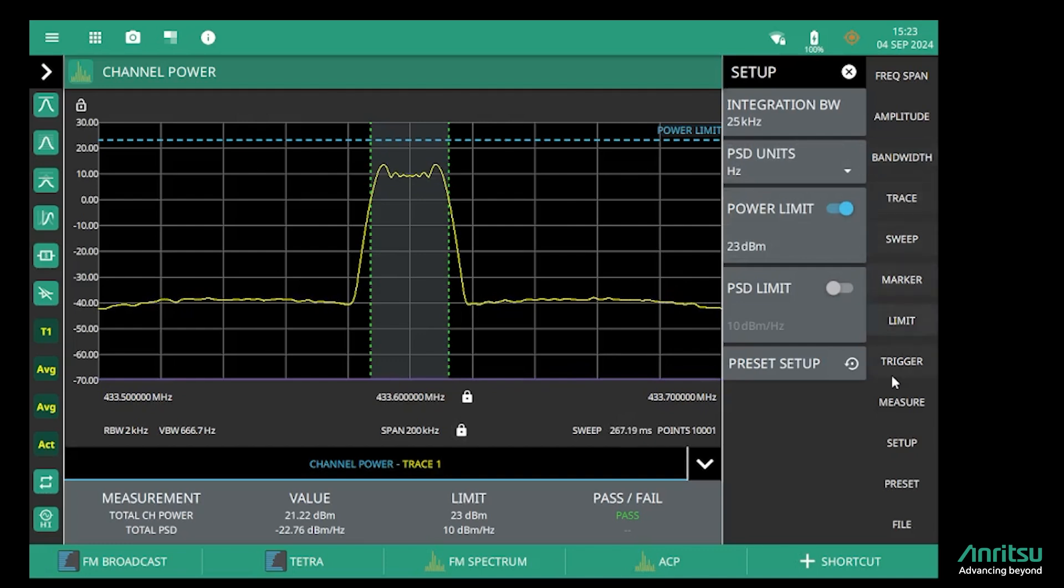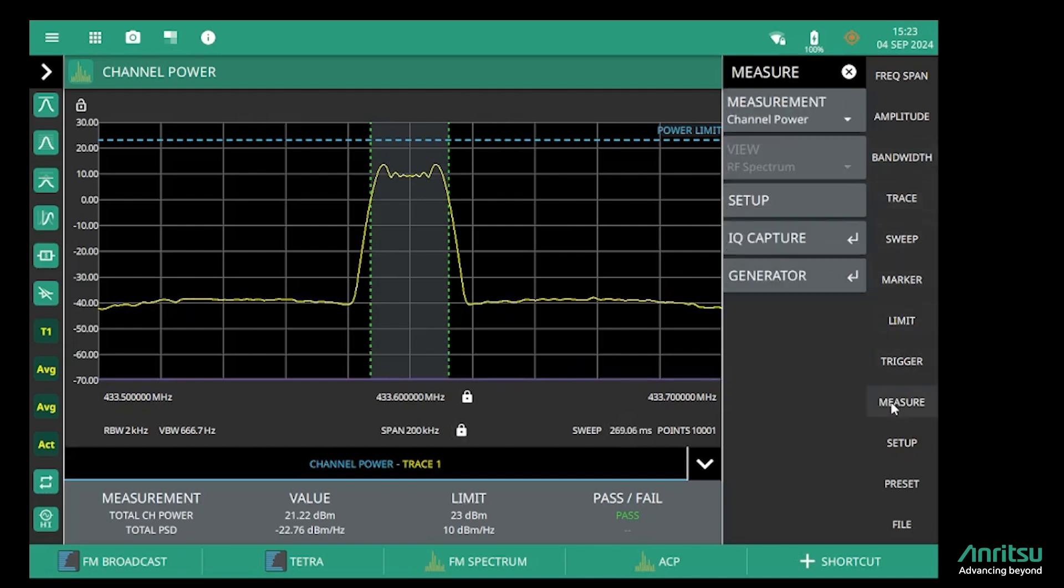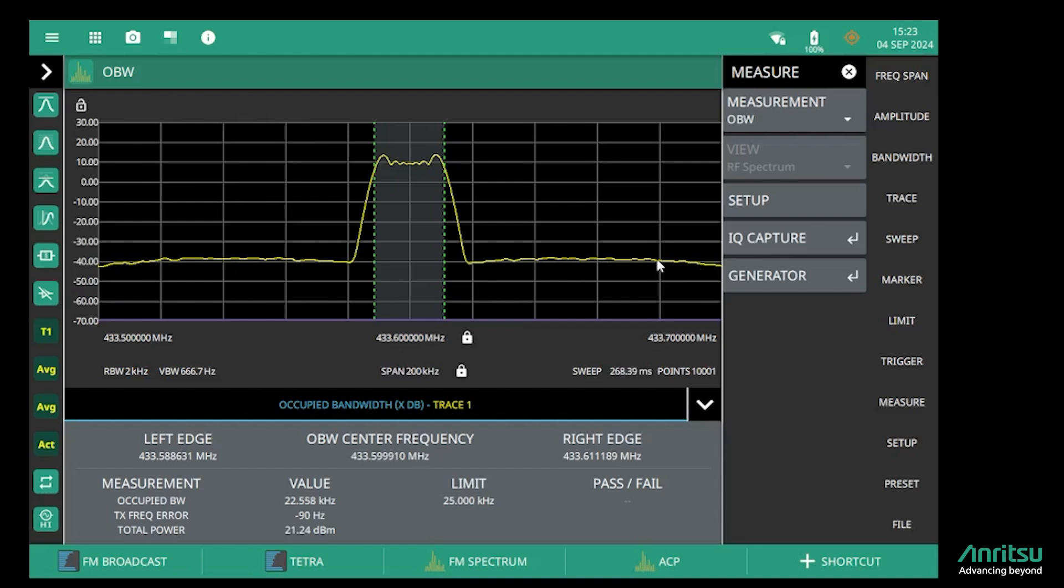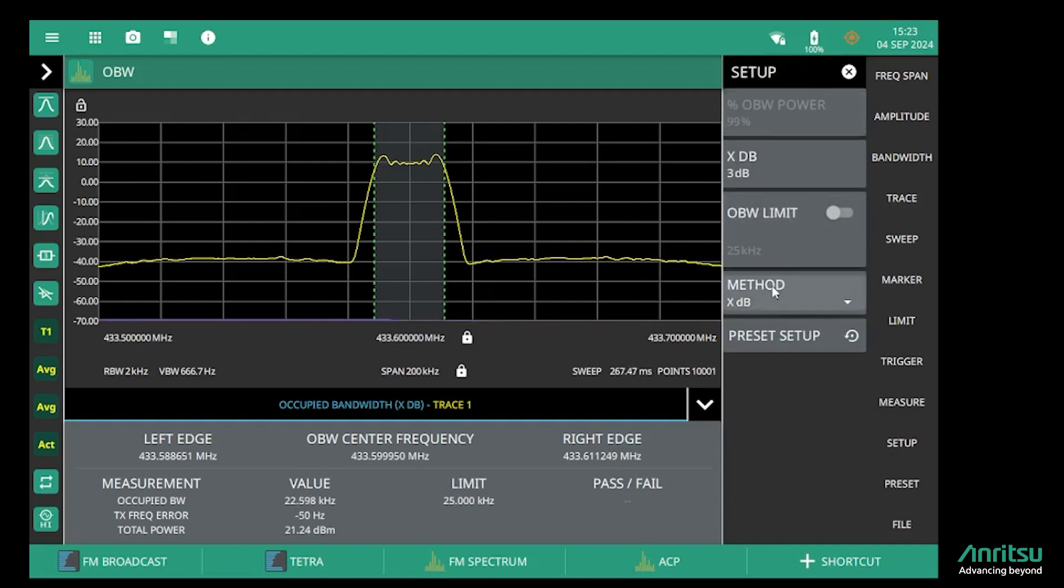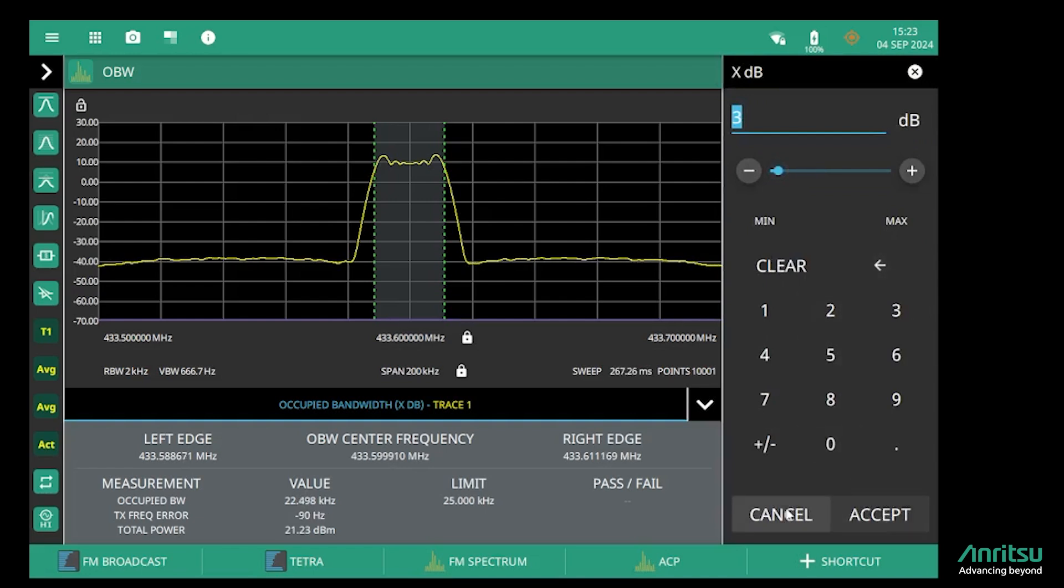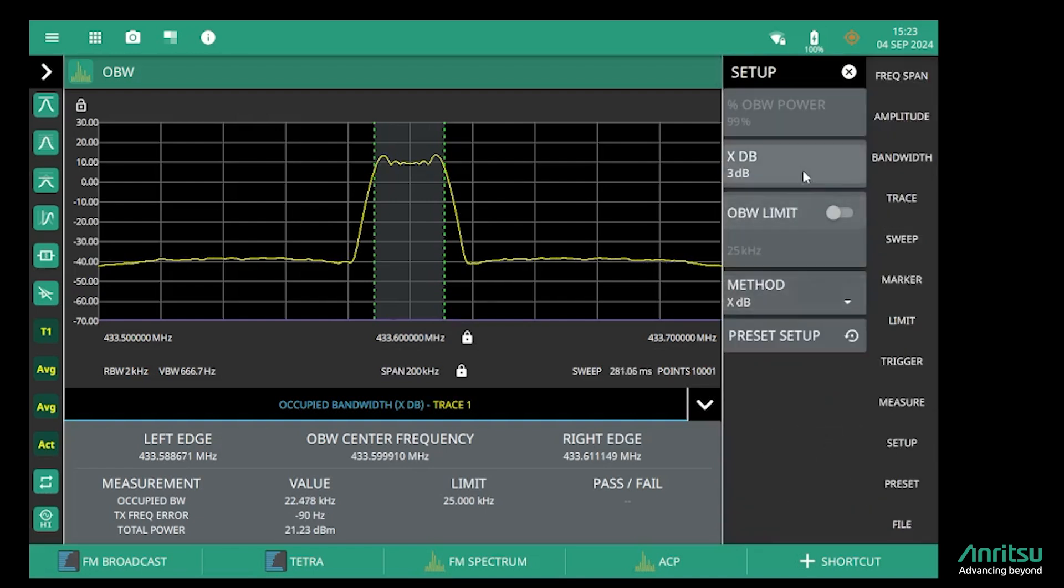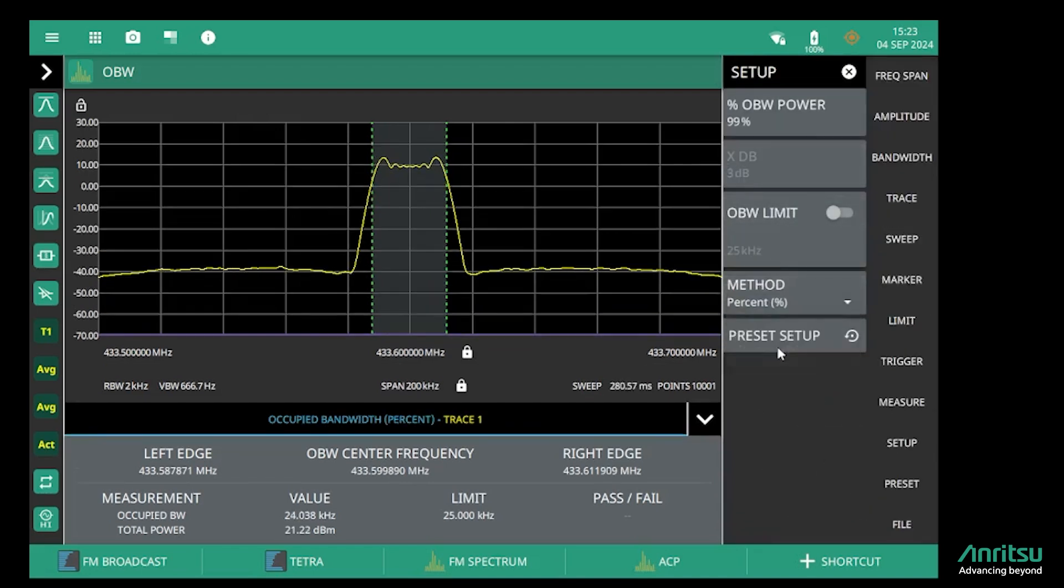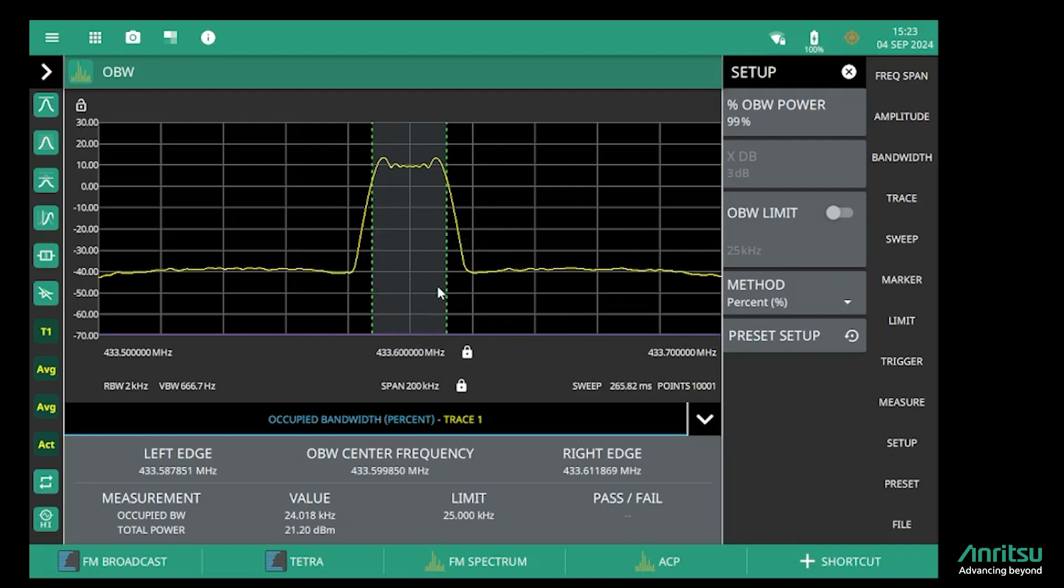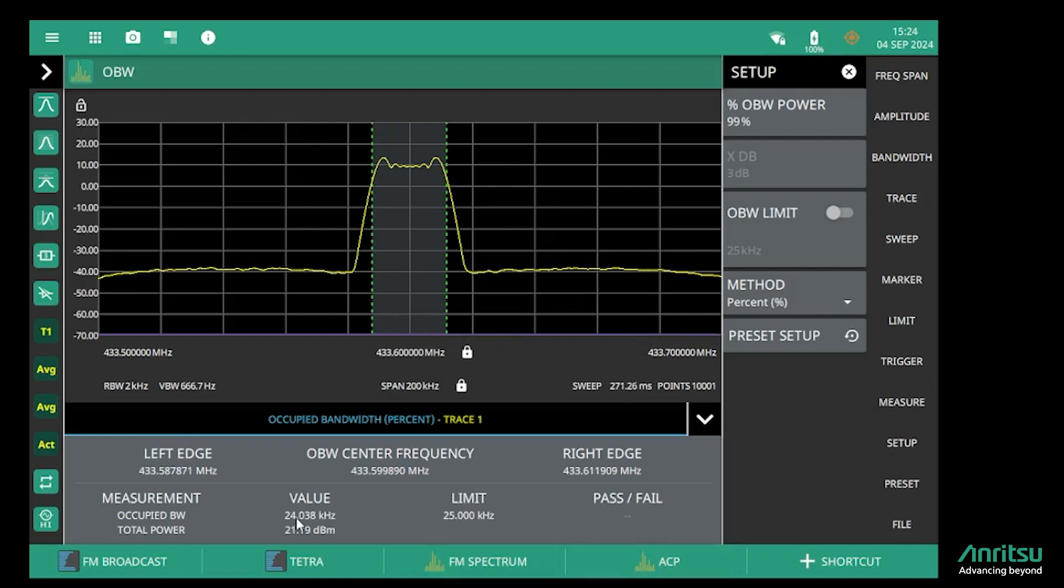The next measurement I want to show is the occupied bandwidth measurement. With occupied bandwidth, there are two definitions: one where we define the 3 dB slope on the channel, and the other where we define the percentage. If we define it as the percentage, that's the 99% of power within these two markers. These two markers are positioned at the 99% of power frequency points, and we see the left and right marker frequencies here, and the 99% of the power is within 24 kilohertz, so within the 25 kilohertz channel spacing of this radio.